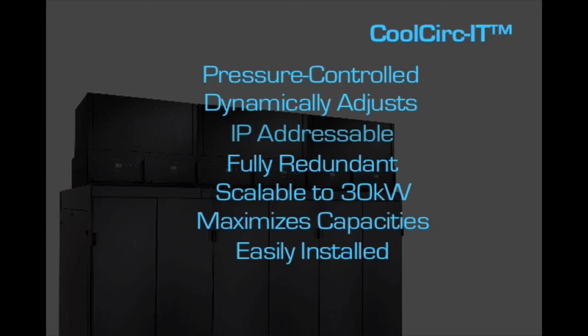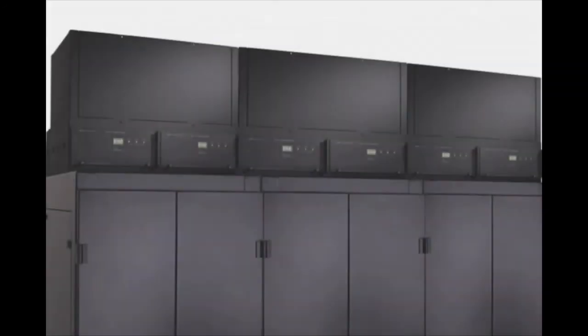No water or piping infrastructure is needed to install or maintain, and the units prevent hot exhaust and cold supply air from mixing. If you want to achieve up to 100% utilization of your cooling infrastructure, try CoolCirc-IT and chill, literally.